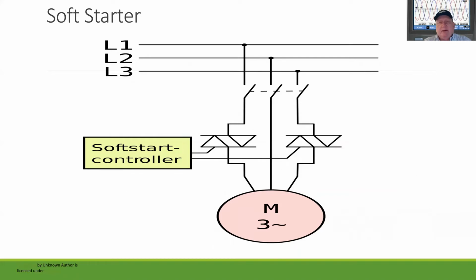The other option that we're going to talk about a little bit today is soft starters. This has been lost a little bit because of the invention of the VFDs that have come on so strong. I still highly recommend them because these devices, once they're up and operating, don't have any losses other than just the wire losses that you had on the original magnetic starter that shows a disconnect switch. And then this is a silicon controlled rectifier. You can see they're diodes that can feed either positive or negative. So when the waveform goes, it passes through, but this can be regulated for how fast.